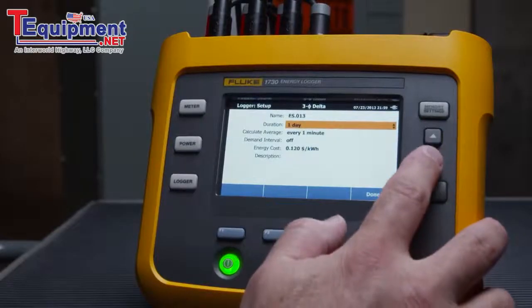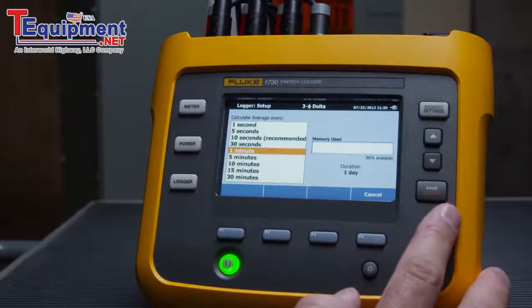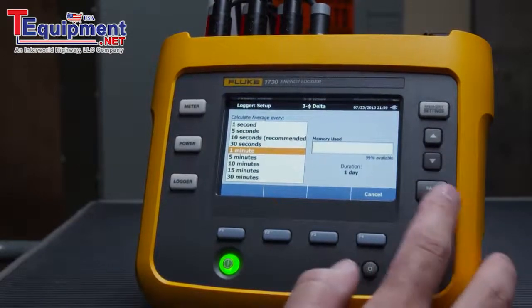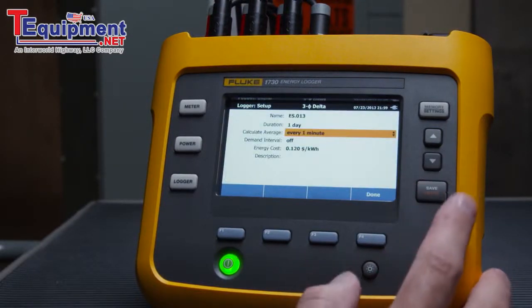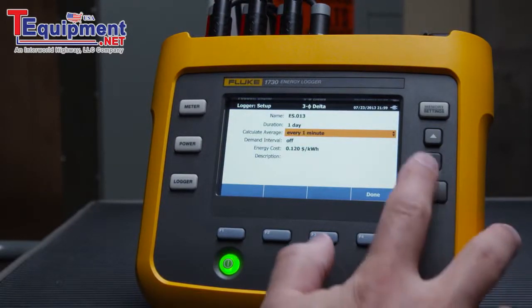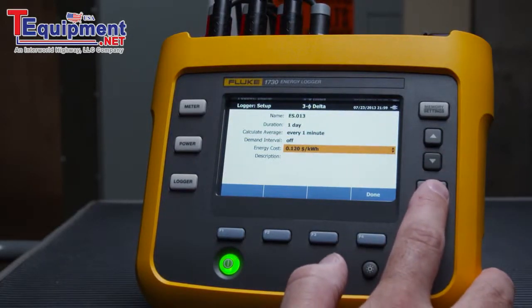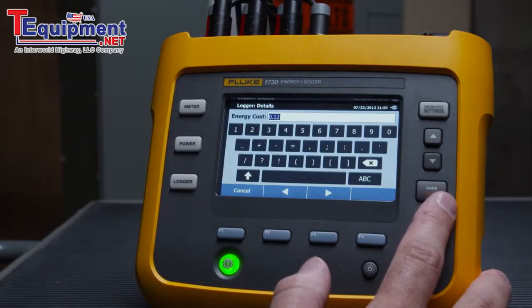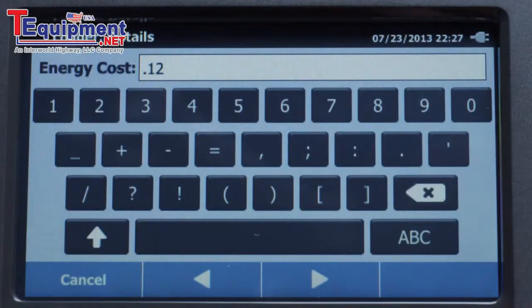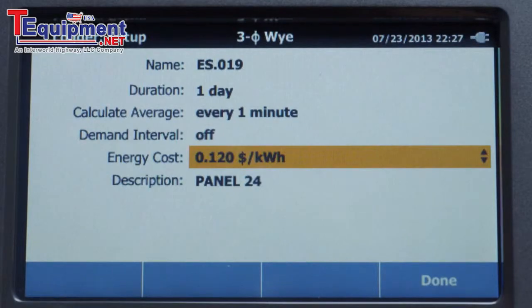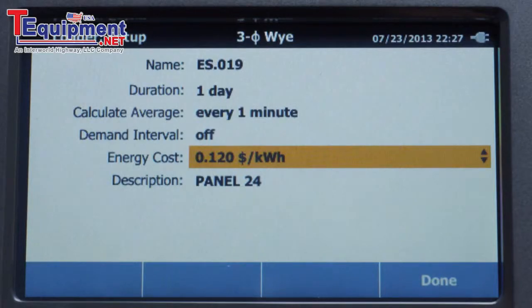Next, we'll select the Average Period. This is the period used to present the data on the trend graphs. If you're logging for an extended time, choosing a short average period will result in a larger file. Energy cost per kilowatt hour can also be selected to track your energy expense. Currency type can be changed in the Settings menu. The file name for your log data is automatically generated — in this example it's ES.019, found at the top of the logger settings list.